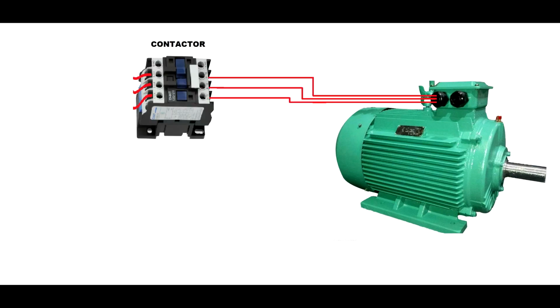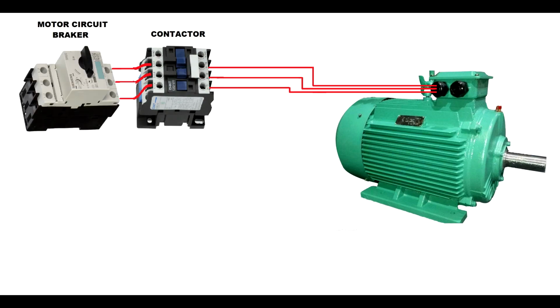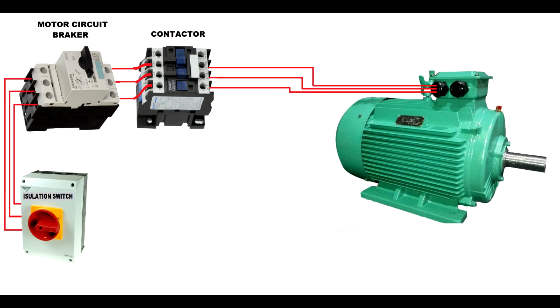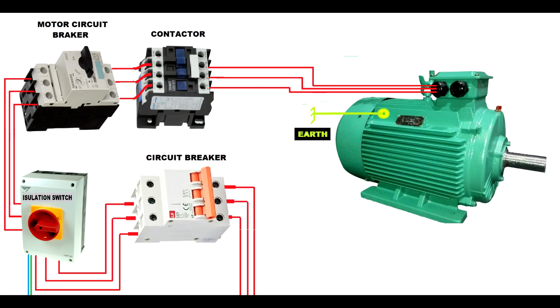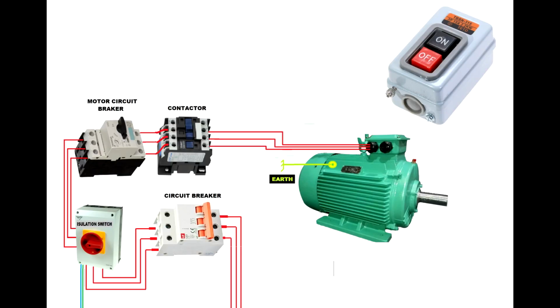So here's your contactor. Now let's see. We want to build a DOL, direct online start. That's a bad one. Anyway, if you want to build that, first you have to choose the motor. Then you have to choose a contactor that has the capability to support the motor load. Also, it's a good idea to use a motor circuit breaker to protect the motor. Going further, you need an isolating switch, because sometimes you have to repair the motor. You have to be safe. Then you have the main circuit breaker, which protects the wires, not the motor. So here's your circuit. Now you need a form of control.